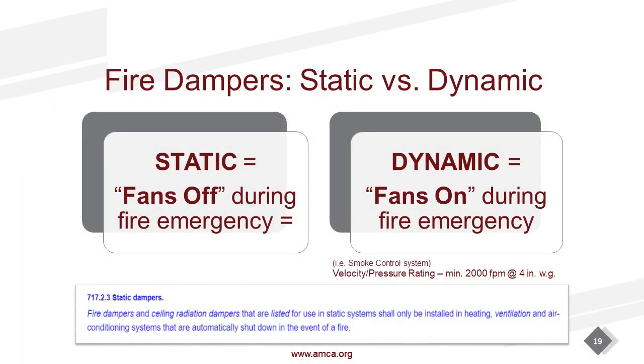The opposite would be a dynamic system. My fans are running. That's either intentionally or unintentionally. Intentionally, engineered smoke control system. I'm using a series of fans, dampers, doors, and other equipment to control, isolate, and move and evacuate smoke. Unintentionally, residential multifamily. I have a unitary heating product in a closet. I've got a ceiling radiation damper. What's telling that residential heating and cooling product to turn off? Nothing. That ceiling radiation damper is now in a dynamic condition. If you want to know more about that, show up at 3 o'clock. We're not going to go into that today. 3 o'clock will be an in-depth look on ceiling radiation dampers. That was such a shameless plug, I apologize.